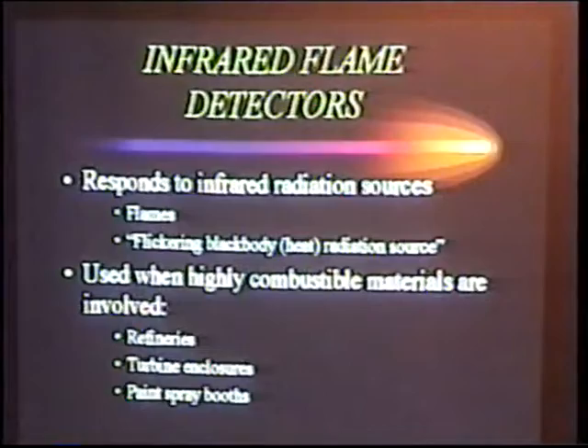Infrared flame detectors, same thing, respond to infrared radiation caused by the flame itself. But IR detectors can also go into alarm if we have a flickering black body heat radiation source. People say, what the heck is that, right? Black body heat radiation source.